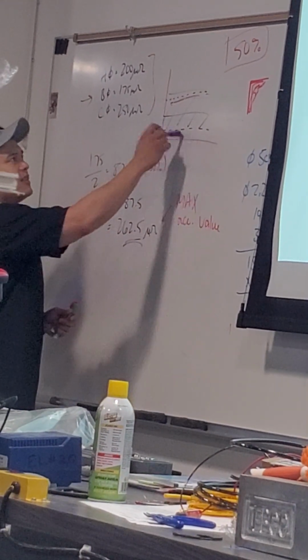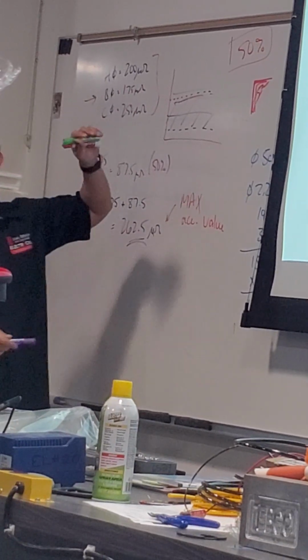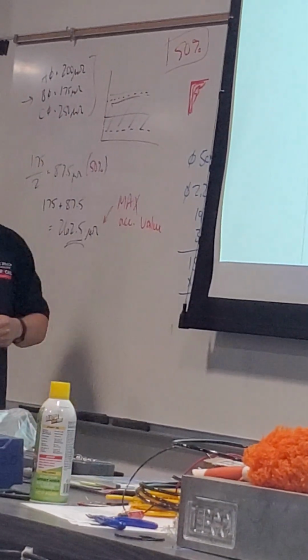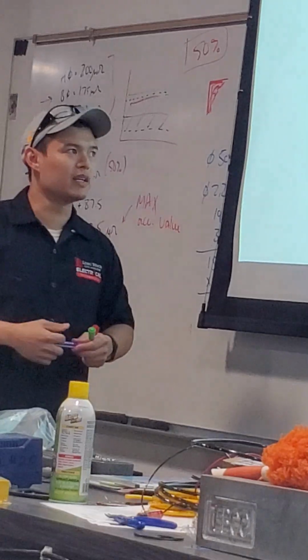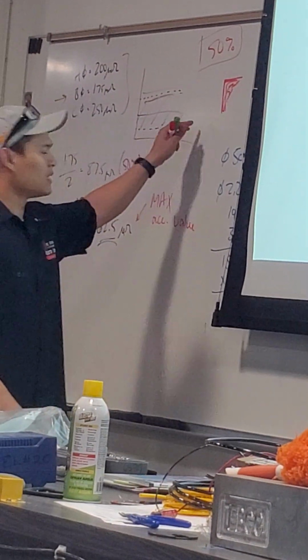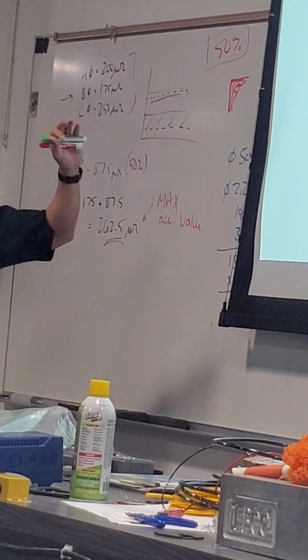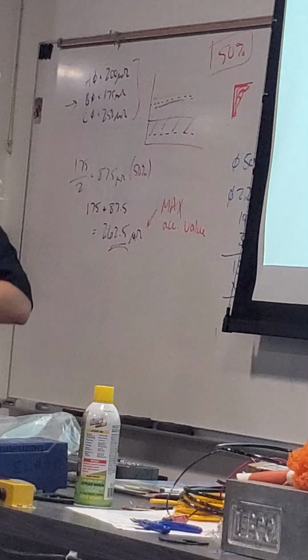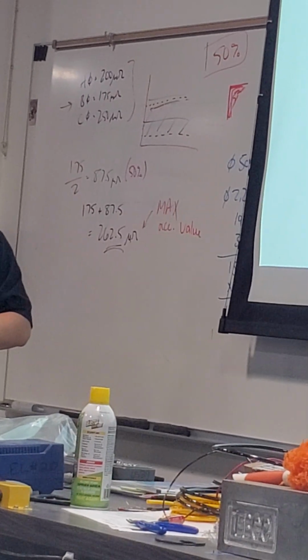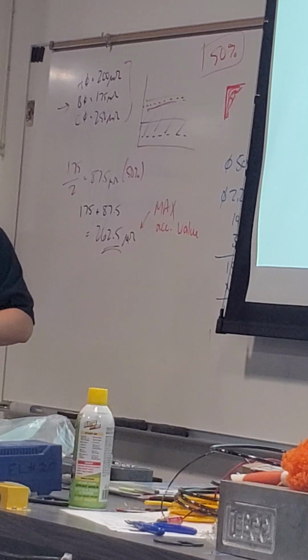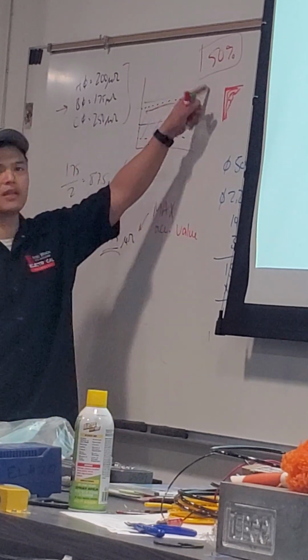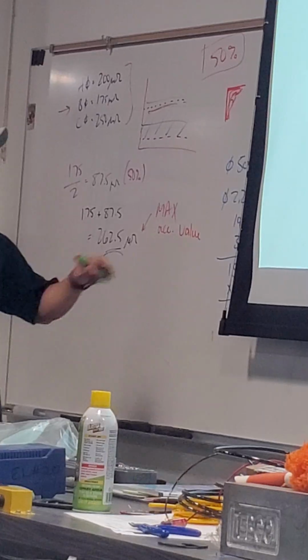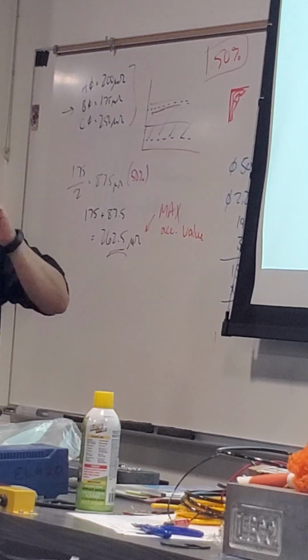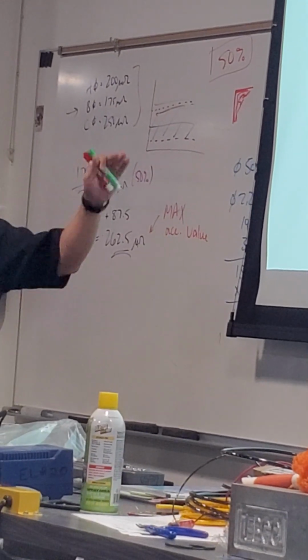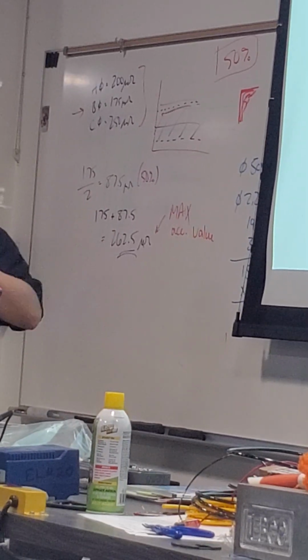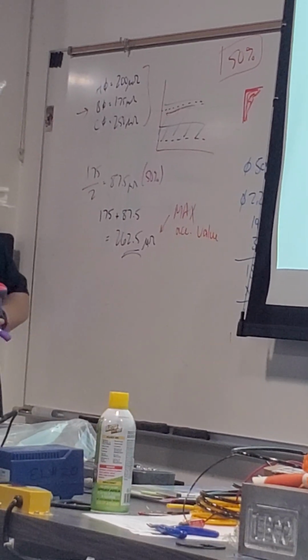So all of a sudden this green one is too high. That means it's subject to more heating, more risk, especially in the long term, because the 50% rule conceptually comes down to wanting consistency between the three phases. A, B, C should be close. The question is how close? Well, that's established by the 50% rule. We can talk numbers and graphs, but in words it just means: are the three values you obtained close enough to each other? That's what the 50% rule really means.